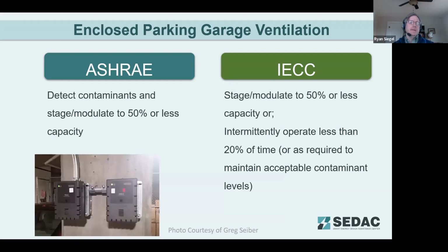So parking garage ventilation. Here it's a little bit similar in that ASHRAE and IECC both allow for the 50% stage and modulation. IECC adds another option, rather than staging or modulating, to intermittently operate the systems for that.